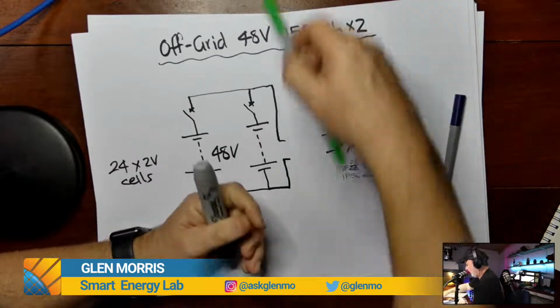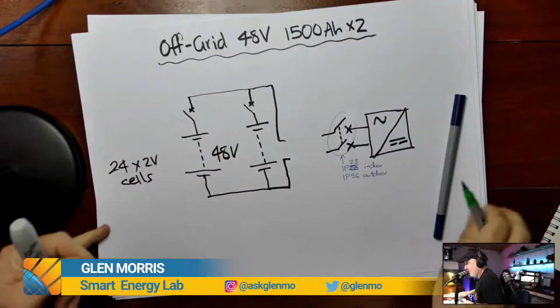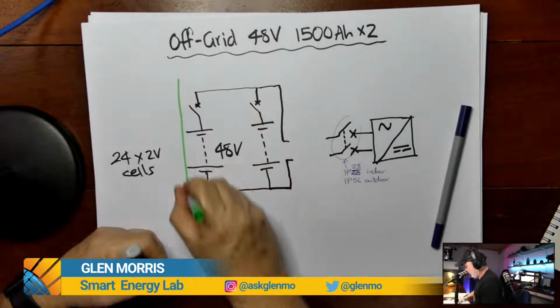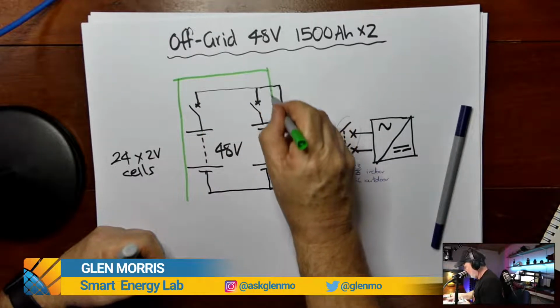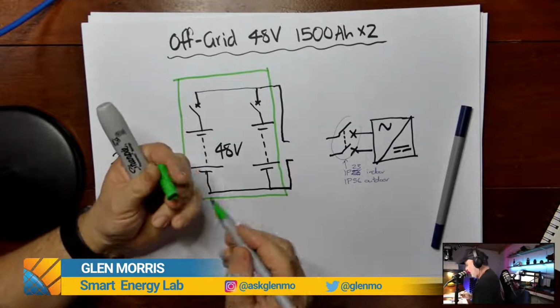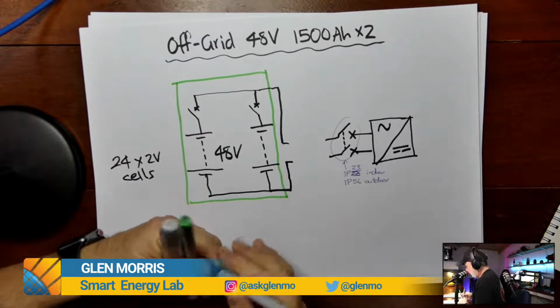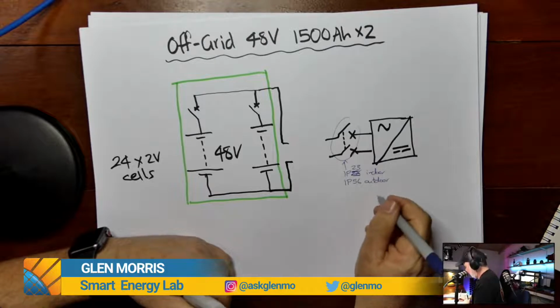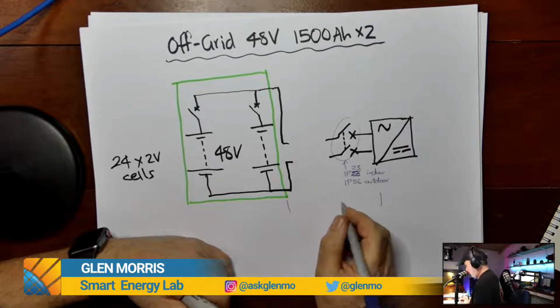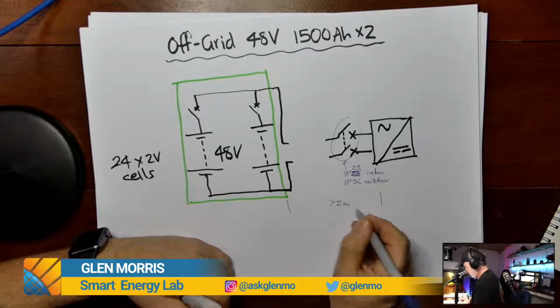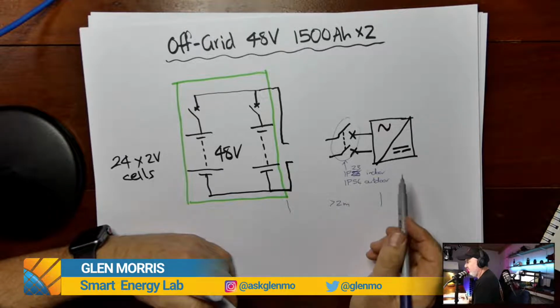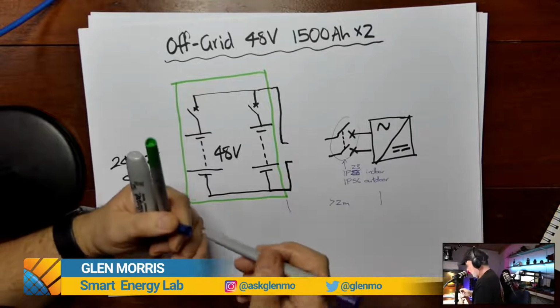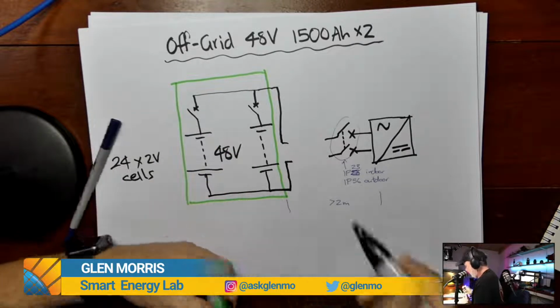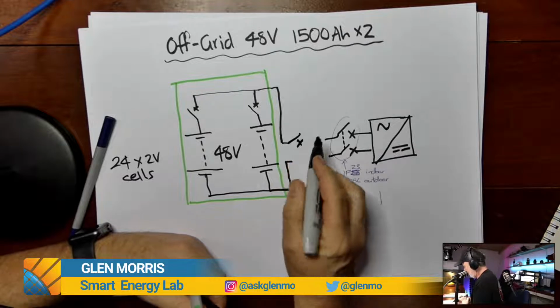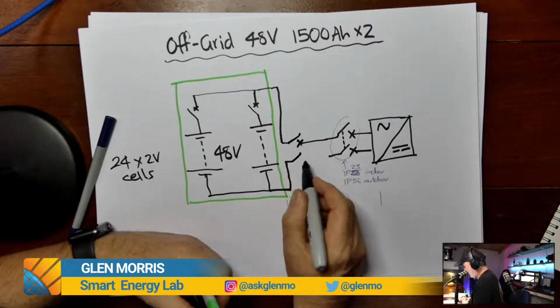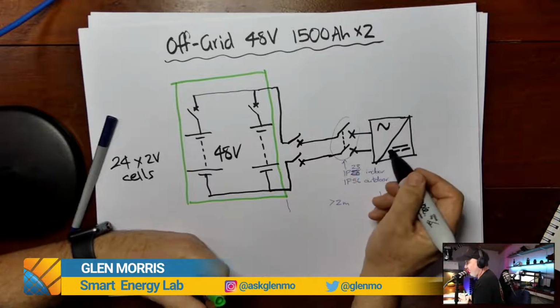Now I'll indicate what the battery system is. So the battery system here is this area here. This is a box that the battery system's sitting in, and it's got some terminals on the outside. Now, if the distance between the PCE and the battery system is greater than 2 meters, then we need to have isolation at both ends of that cable. So we would need to have isolation here adjacent to the battery system, and isolation at the PCE.